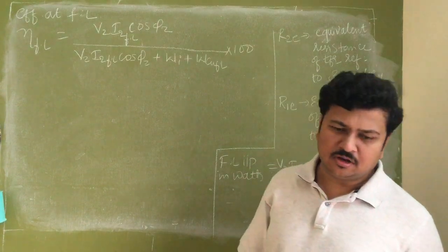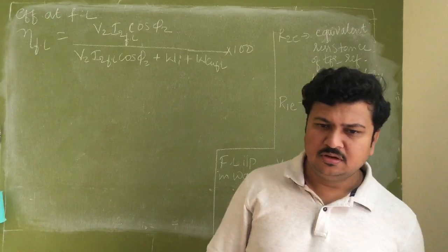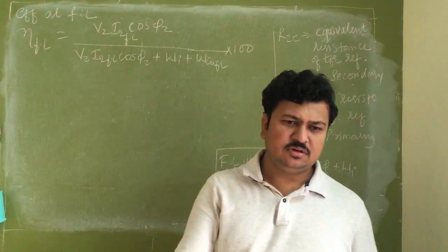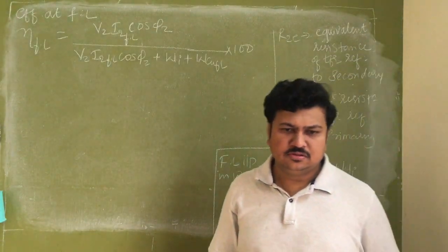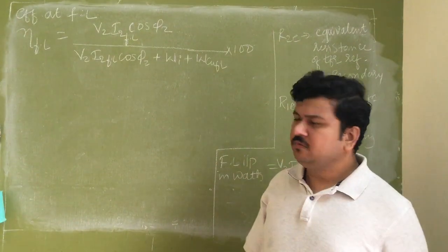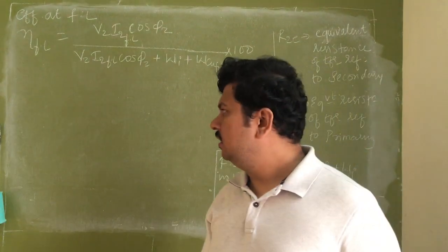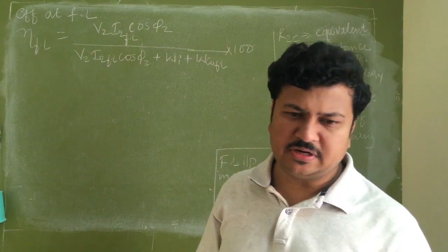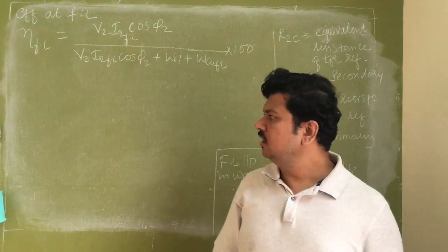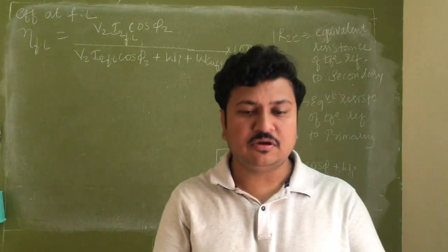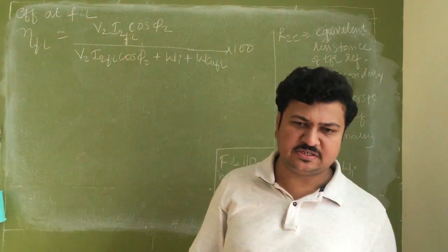The 12 tube lights are each around 36 or 40 watts. So 12 times 40 is 480 watts. And for 5 fans, let us take 100 watts each, 500 watts. So 980 watts. Let us take 1000 watts. So the entire connected load is around 1000 watts.